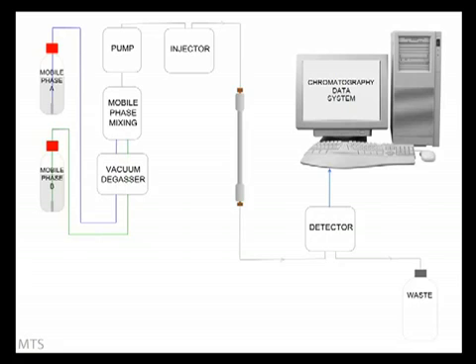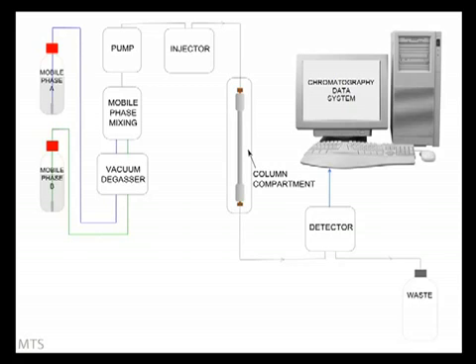Another instrument which is typically included in an HPLC system is a vacuum degasser, since all air needs to be removed from the mobile phase for optimum performance. Temperature is an important method parameter which needs to be controlled in HPLC analysis. For this reason, the column is often housed in a compartment which can be temperature controlled.